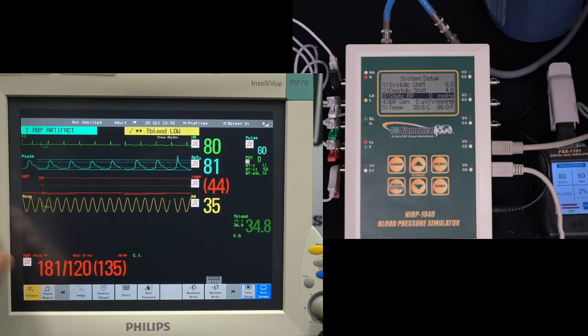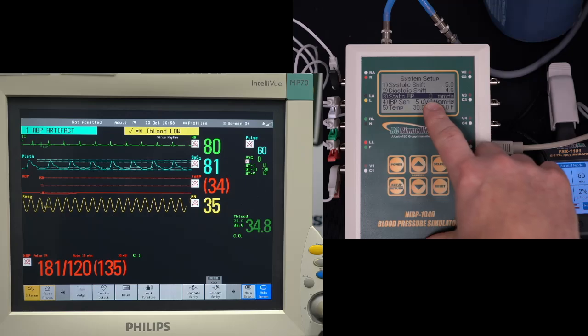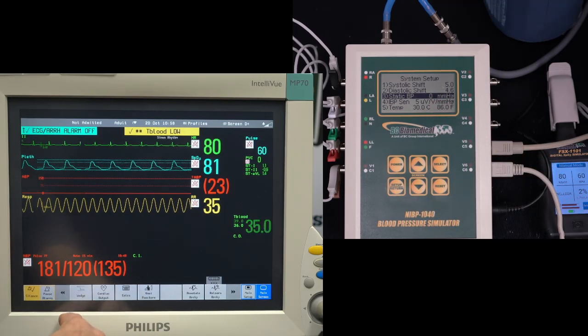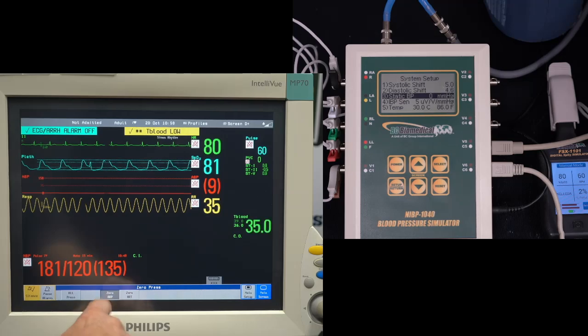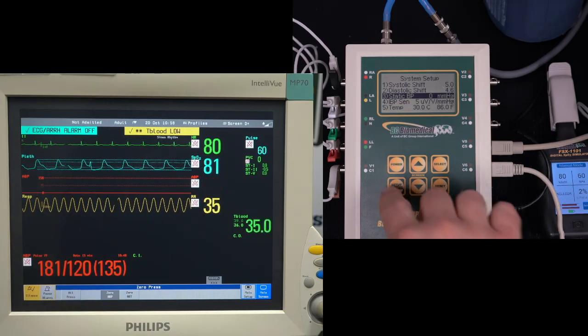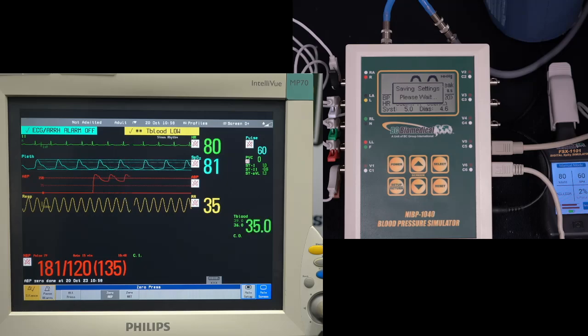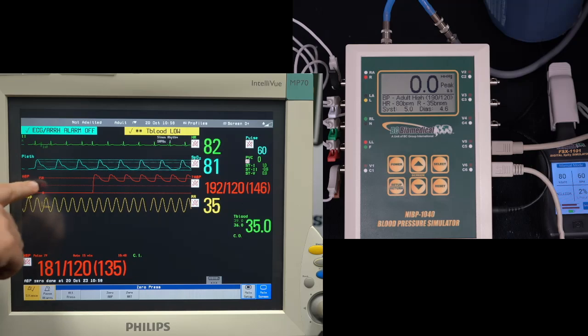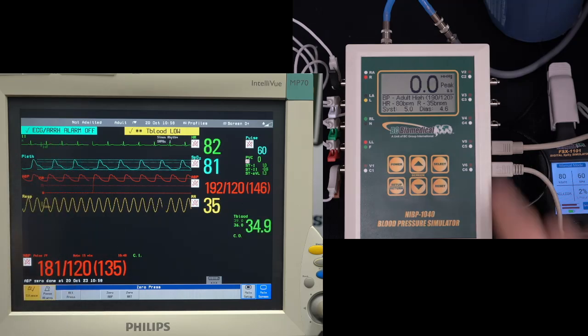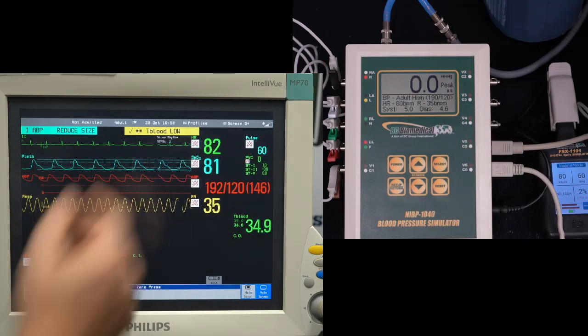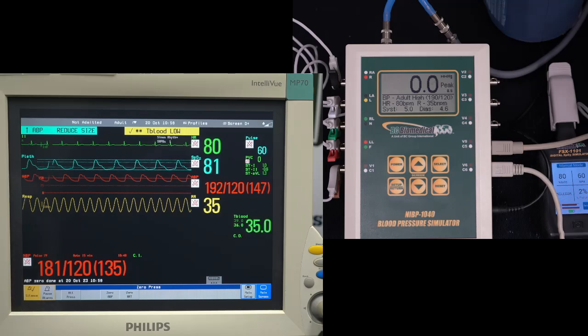So to do the 0, that's where I came in here. I came into the menu, set it to 0, and then on my monitor, all I have to do is tell it that I want to do a 0, and we're measuring the ABP, so I 0 ABP. Now it should 0 that reading, and once we exit that menu, we'll be back in the dynamic invasive blood pressure, and those readings should match. We're set to 190 over 120, and we got 192 over 120 on the monitor. Okay, so that is how to do all of the basic testing.